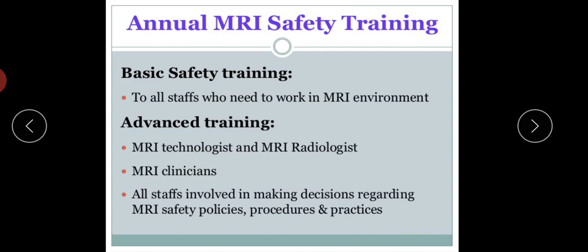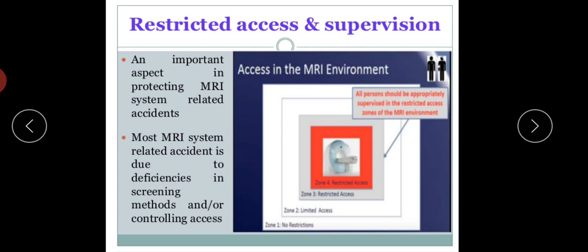Restricted access and supervision is an important aspect in protecting against MRI system related accidents. Most MRI system related accidents are due to deficiencies in screening methods and/or controlling access. So this is zone 3. Zone 1 is where there is no restriction. Then there is zone 2 with limited access, zone 3 is a restricted area, and zone 4 also has restricted access. All persons should be appropriately supervised in the restricted access zones of the MRI environment.